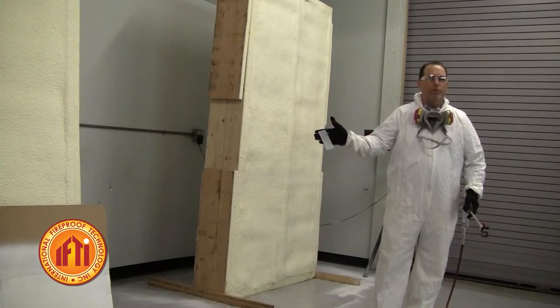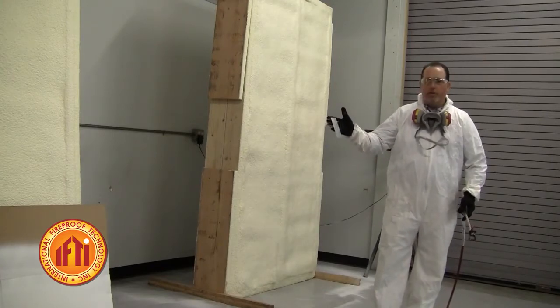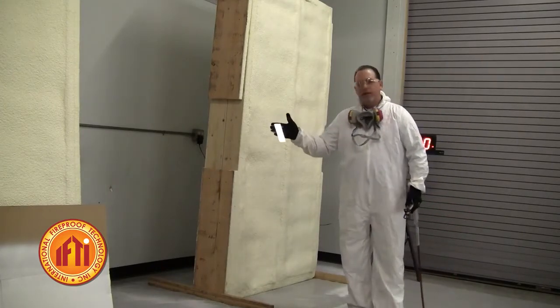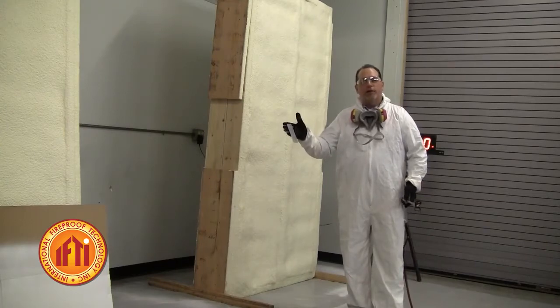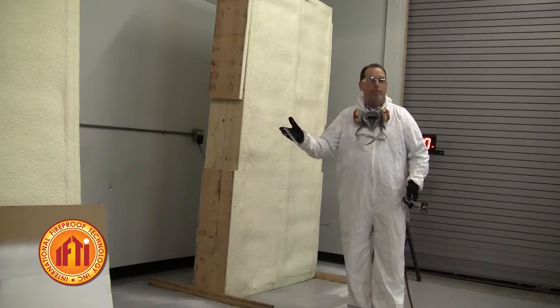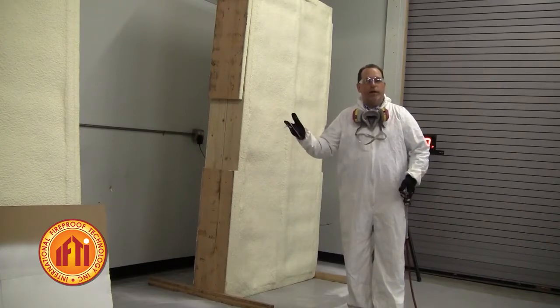One, you've got a nice smooth surface to work with. So when the coating goes on, it's going to be the same as what you're putting here. The second thing is once it dries, you can actually do a dry film thickness with an electronic meter.